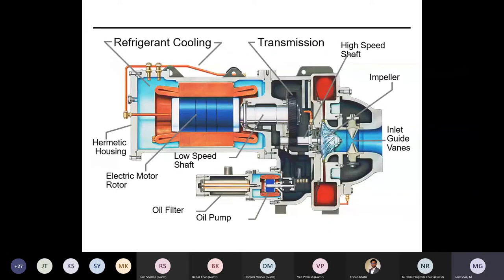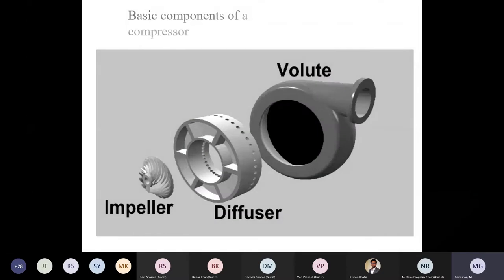Then we come back to centrifugal compressors. By virtue of their large volumes, they can handle large amounts of refrigerant vapor. Here the basic components are the guide vanes, which act like a valve, and an impeller. The gas passes through the impeller at high speed and goes into the volute. Again, as explained, it can be direct driven, that means open type, or semi-hermetic, where the rotor and stator are part of the shaft, with high speed, then low speed, then coupled and driven. Generally a forced oil pump is there because of the high pressure application. In a centrifugal compressor there are three major components: impeller, diffuser, and volute.